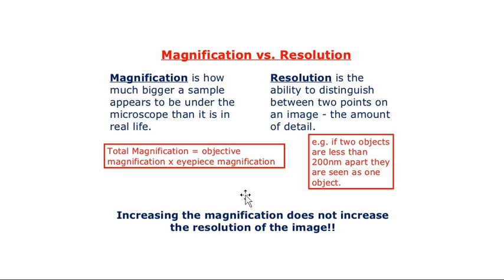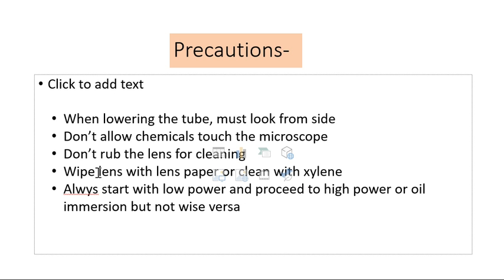Now, some precautions during focusing: When lowering the tube, look from the side while using coarse adjustment. Don't allow chemicals to touch the microscope. Don't rub the lens for cleaning—wipe with lens paper or clean with xylene. Always start with low power and proceed to high power or oil immersion, not vice versa.